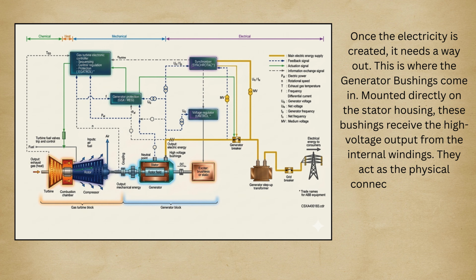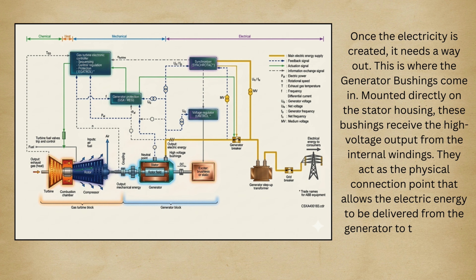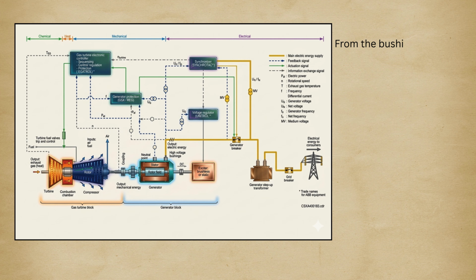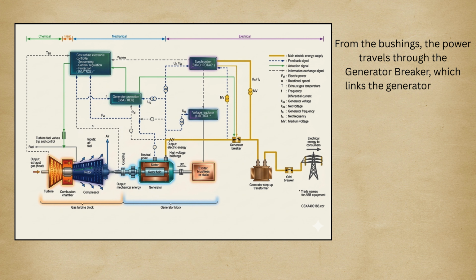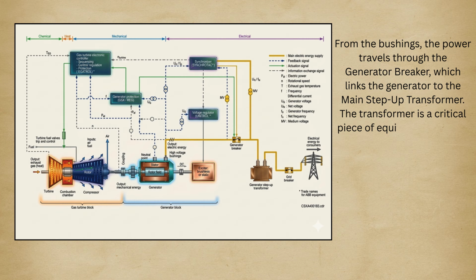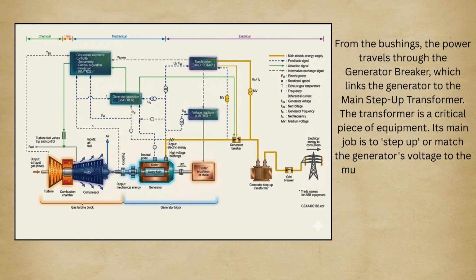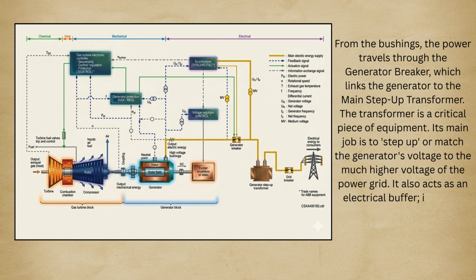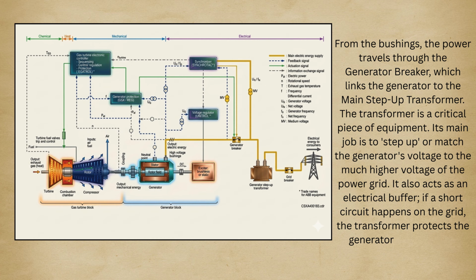They act as the physical connection point that allows the electric energy to be delivered from the generator to the outside world. From the bushings, the power travels through the generator breaker, which links the generator to the main step-up transformer. The transformer is a critical piece of equipment. Its main job is to step up, or match the generator's voltage to the much higher voltage of the power grid. It also acts as an electrical buffer. If a short circuit happens on the grid, the transformer protects the generator from damage.